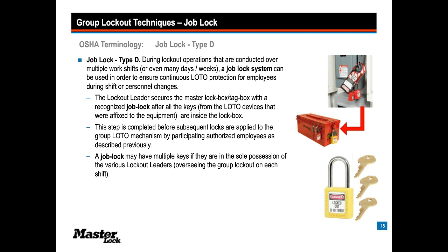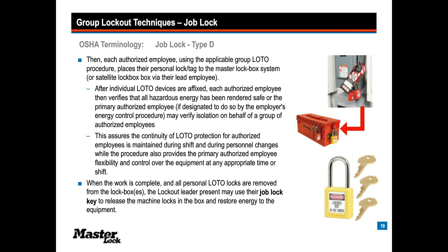I think I got a little ahead of myself as far as the process. When the work is complete and all personal lockout locks are removed from the lockbox, the lockout leader present may use the job lock key to release the machine locks in the box and restore energy to the equipment.